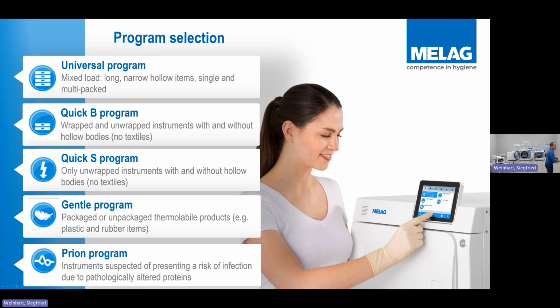You've then got gentle programs and you've got prion programs. We don't really use prion programs in the UK. Occasionally we will use gentle programs. Gentle program is typically a 121 temperature. There are some surgical instruments that can't go through 134 sterilization, so they would require a 121 sterilization. Some bite wings, things like that, can't go through the higher temperatures. So have a unit that's got a good selection of programs and make sure that we select the right program for the load types that we're putting in there.